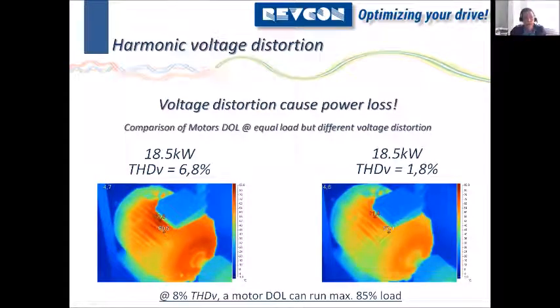Okay, so what kind of problems are caused by harmonics, basically? Voltage distortion causes power loss. That's a fact, and you can read this in some official documents. I saw a Danfoss seminar two days ago, and they refer to the IEEE saying that with 8% THDV, a motor running direct online can only run up to 85% load. That means if you have a high distortion, and that's actually the limit in the IEEE, if you really go to that limit, you cannot run your motor at full load anymore. It can only run 85% load. And I think that's quite a warning to understand about harmonics.